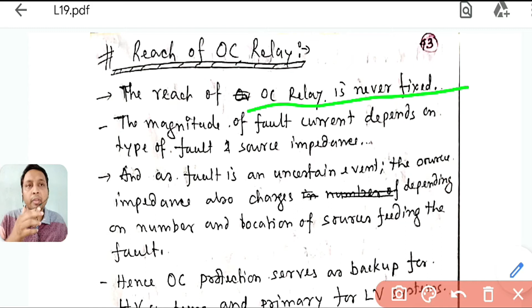So what was the problem in the overcurrent relays, due to which the distance relay came into the picture? One of the main problems of the overcurrent relay was the reach, because it was never fixed. We gave a hint in the initial classes that the reach is never fixed. So we'll see how the reach is not fixed. Why does the reach of the relay change? Because the magnitude of the fault current keeps on changing. That depends on the fault and the source impedance.